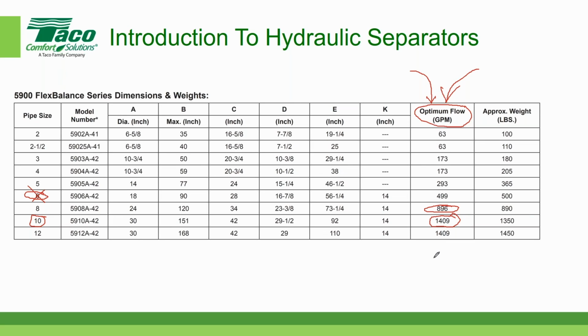That's a great question. So what we know is that in some cases, let's just go back here. Yes. So in some cases, the 10-inch would have a maximum flow of 1409. The actual size of the separator, if you look at the diameter, they're both 30 inches. So this 30-inch can accommodate a 12-inch connection, because in some cases, someone may want to have a 12-inch connection, but it cannot exceed 1,409 gallons per minute. So that's more to accommodate the different size pipes that are out there, so that the 12-inch can't accommodate more flow than the 10-inch, but we offer it in a 12-inch to make it more convenient, because some people will have a 12-inch pipe connection rather than a 10-inch pipe connection. So it's more convenience than it is anything else.